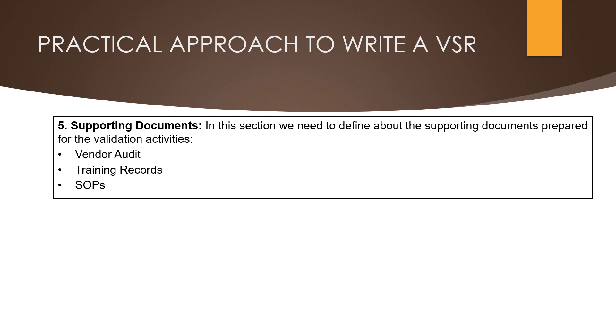Next is standard operating procedures. Here we need to mention the statement that relevant SOPs for the system were prepared, approved, and made effective. We also need to provide details of all relevant SOPs such as SOP number, version number, title of the SOP, and SOP effective date.